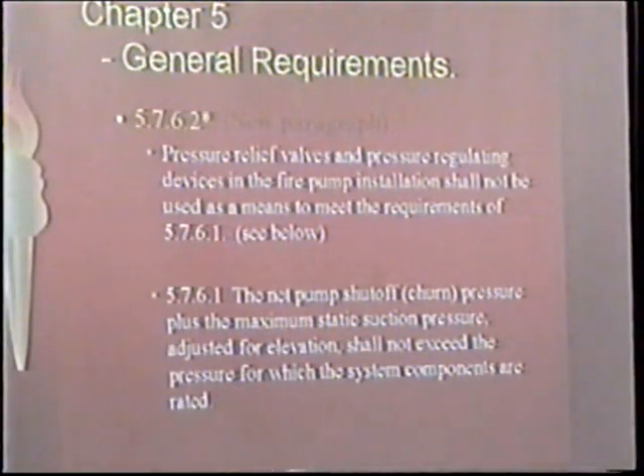But Mark, you're basically still allowed to put a suction control valve, is it not? Yes. Right. Same thing. Well, wait. No, not really. Because there you're dealing with an inadequate water supply, and the pump suction control valve is going to restrict flow, not necessarily pressure. The normally closed valve, once it's open and you've got over 20 pounds or 15 pounds of pressure, is going to be wide open if there's flow, and it's not going to prevent any excess pressure from entering the system.